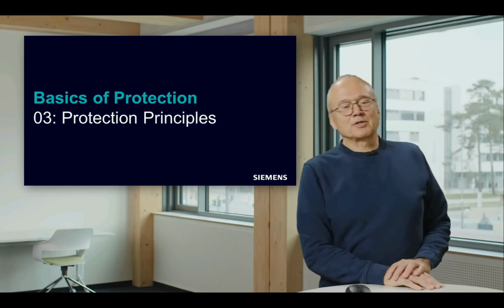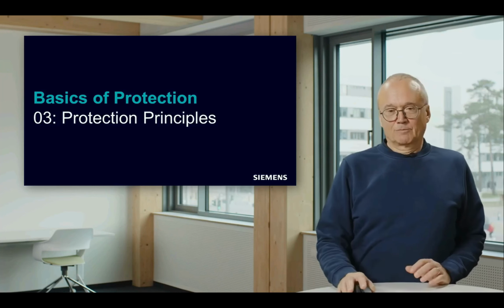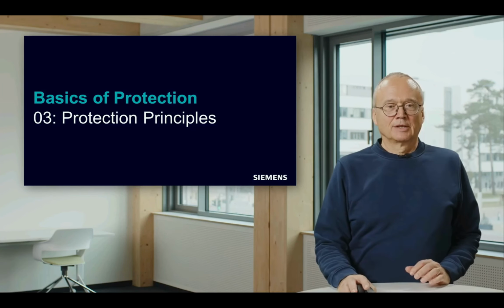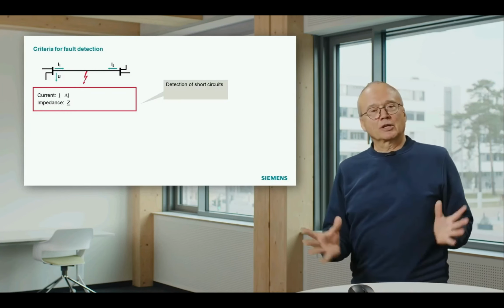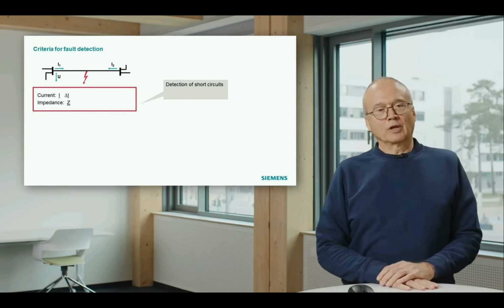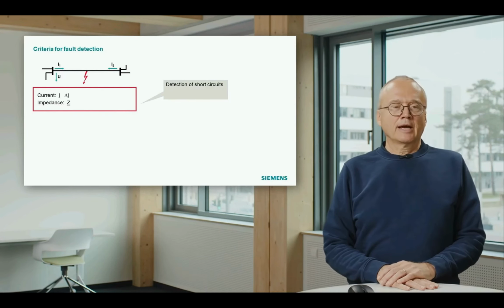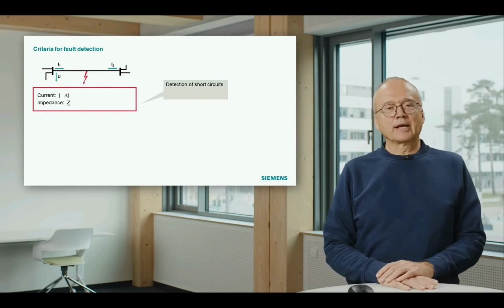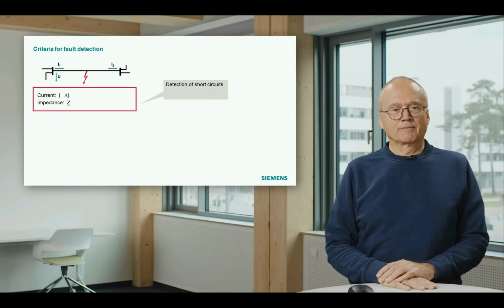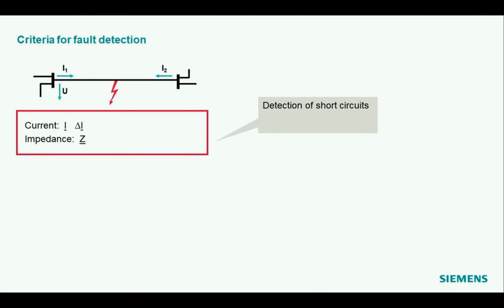Which protection principles are available to detect short circuits? Let's look at this picture. Imagine we have a line and we have a protection relay, maybe on both ends of the line. They can measure the voltage and the current. And now, how can we detect that there is a short circuit on the line? There are basically 3 principles available to do that.